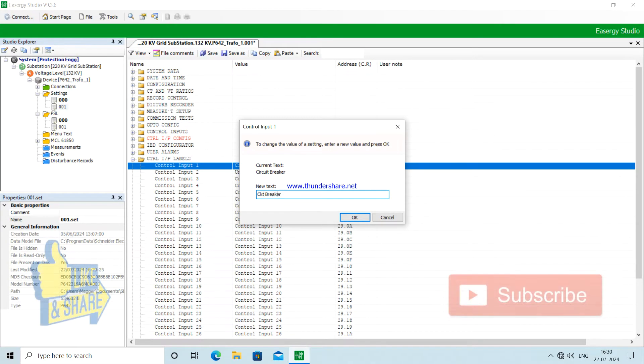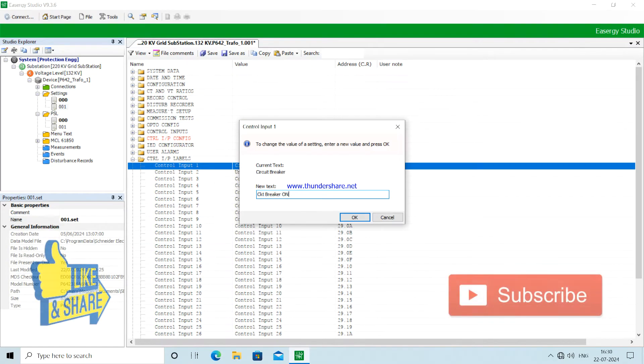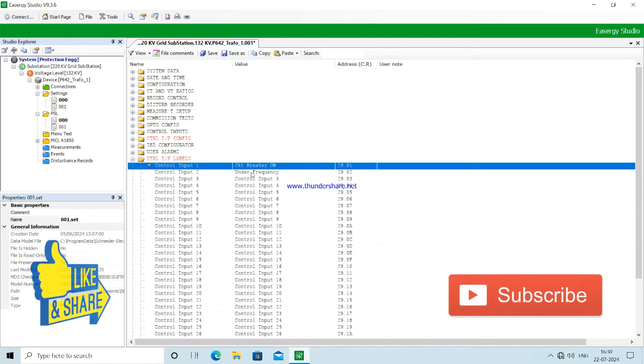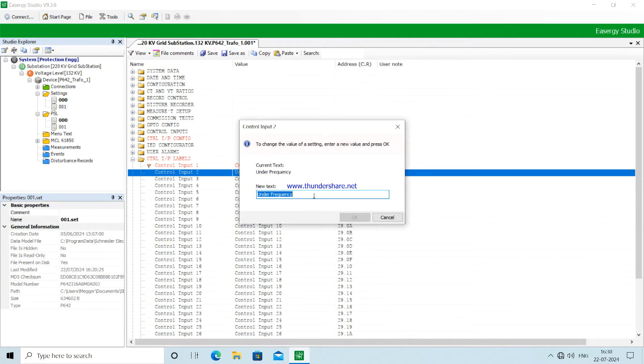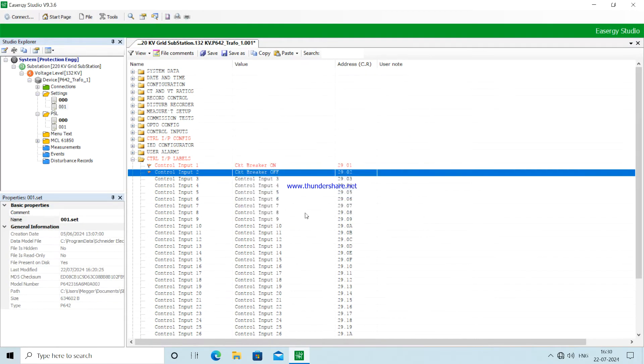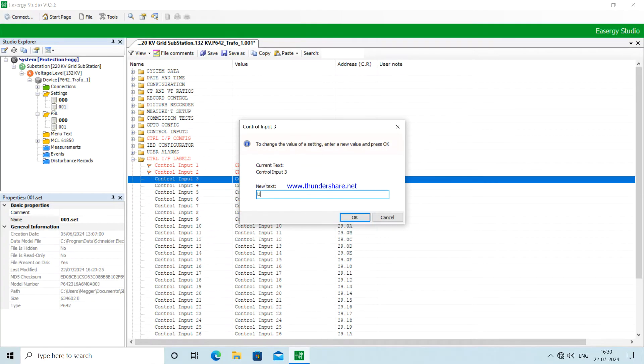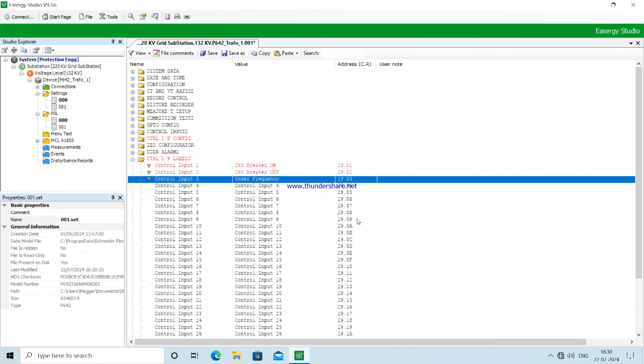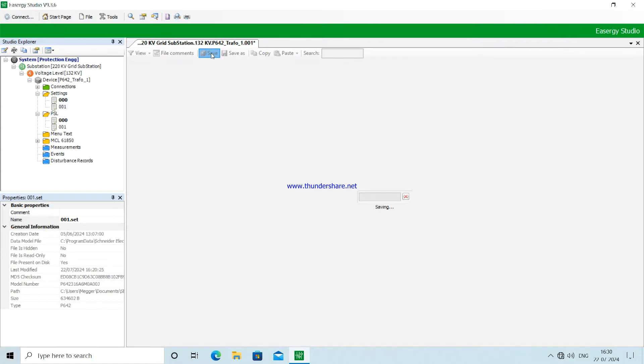Now we are labeling the control input names because these will be displayed on the screen of the relay. There will be three names displayed: one for circuit breaker on, one for circuit breaker off, and the third for under frequency enable or disable. For that we need to enter the names in the control input labels.